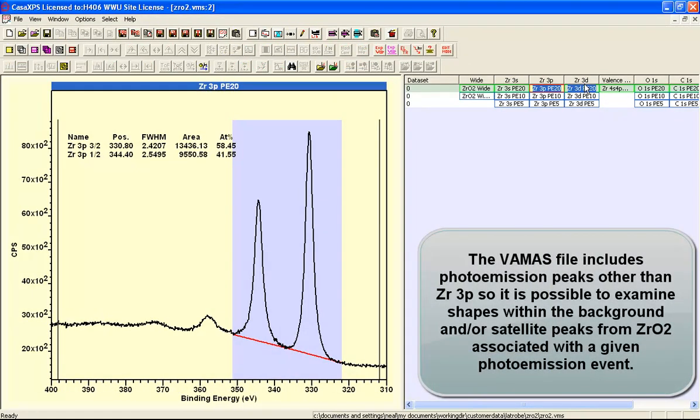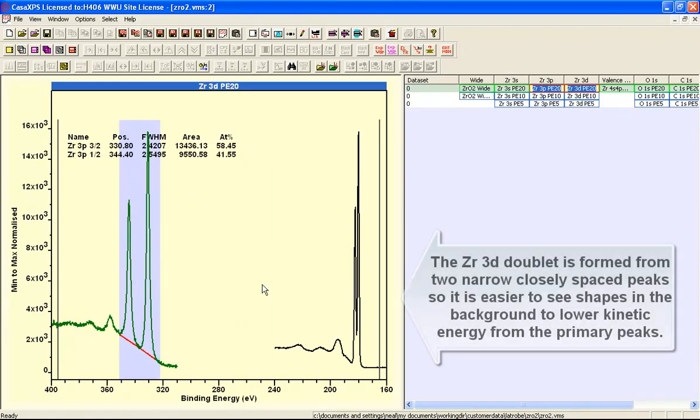If we look at the zirconium 3D and overlay these two together we've got two different photoemission lines. The 3D has produced a doublet also but they're very close together and they're narrow peaks. However you can see because of the narrowness of these peaks that there is significant structure in the background and we also see a similar structure here.